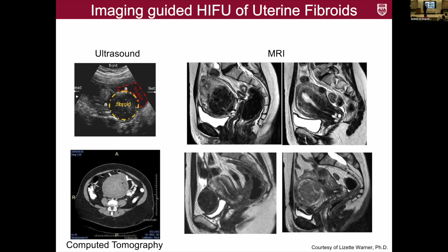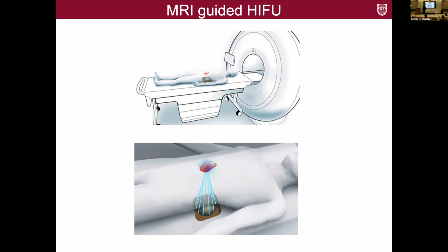You can see here the setup. We put the patient on the tabletop. There's the lesion that we try to treat. We have a special ultrasound mirror system that is under the patient, embedded in the patient table. Then we move the patient inside the bore and try to position the patient exactly in the isocenter of the bore, because the image quality of the MRI is best in the isocenter. And then we start the treatment with the HIFU pulses.